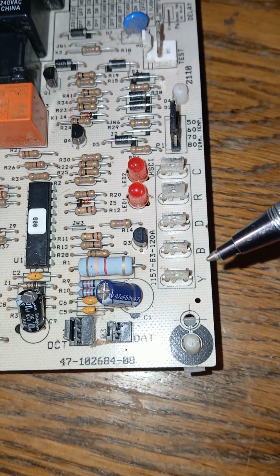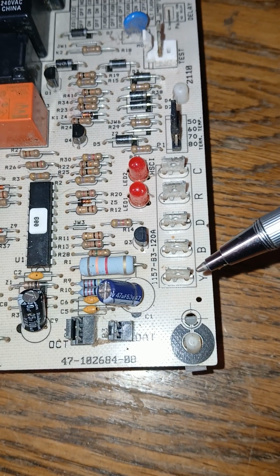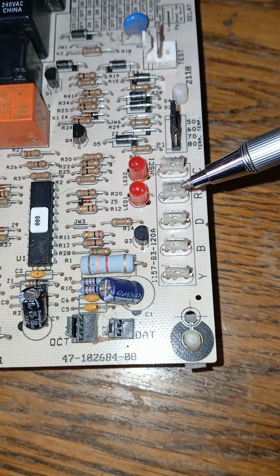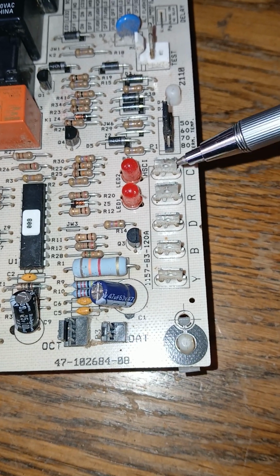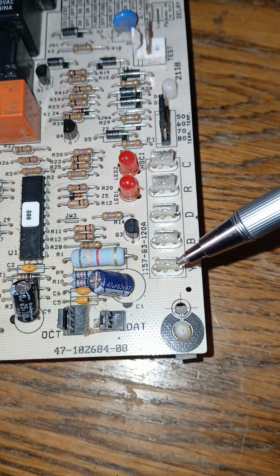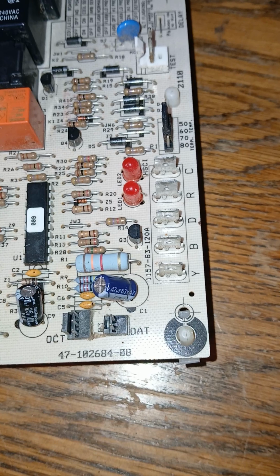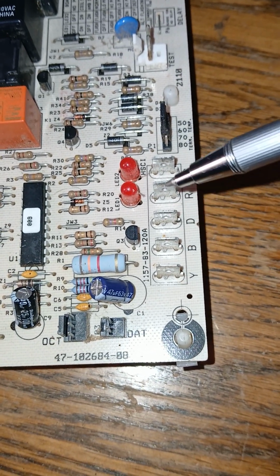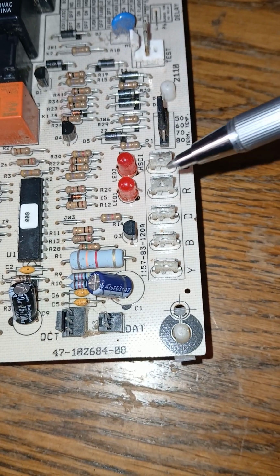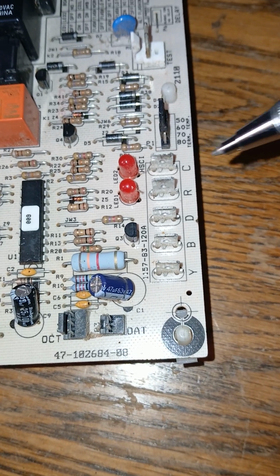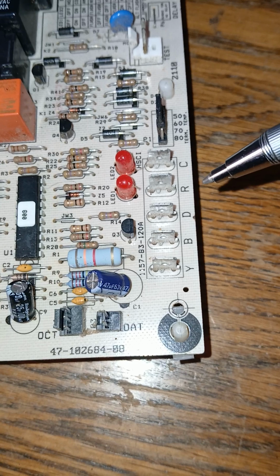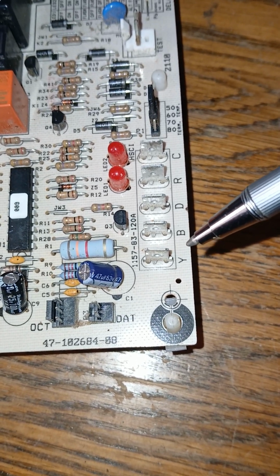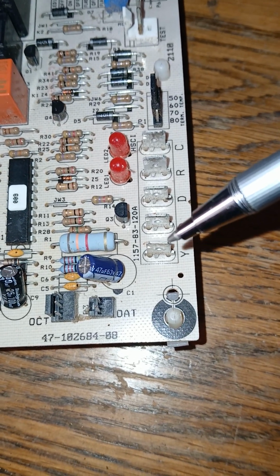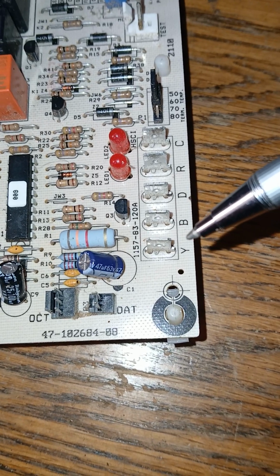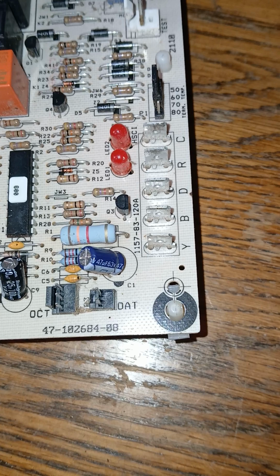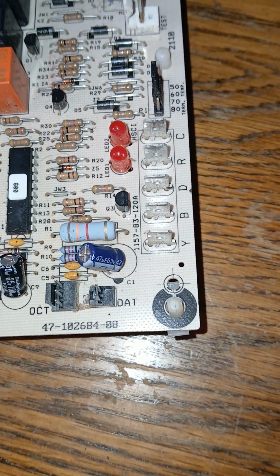But in order to power the Y wire up, I'm thinking the red and the C wire need to be powered up, and then it has to jumper over, and this may be done, I'm not certain, in the thermostat, but whenever it closes. So you've got 24 volts here, then you would have 24 volts here, and then this would be the outgoing here for, I'm thinking, 24 volts on the common, the blue, the red wire, and then the Y would normally be a yellow wire. It's not engraved in stone, but if you could keep it color coded, then one knows it between the transformer, the thermostat, and the defrost control board.